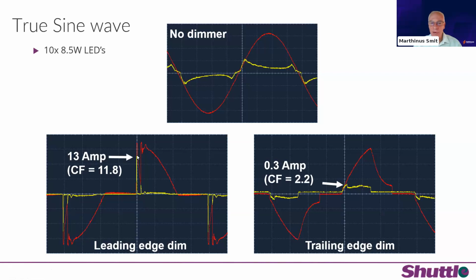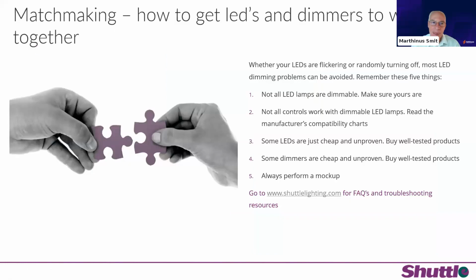Now 13 amp, that is 2.5 kilowatt. Whereas if you dim that on a trailing edge dimmer, you can see that your crest factor comes down to 2.2, and you have a 0.3 amp peak current into your inverter, 46 times less. So when it comes to inverters, and solar inverters and so on, do pay attention to your dimming requirement and your LED requirement, because it can actually catch you very, very unaware.